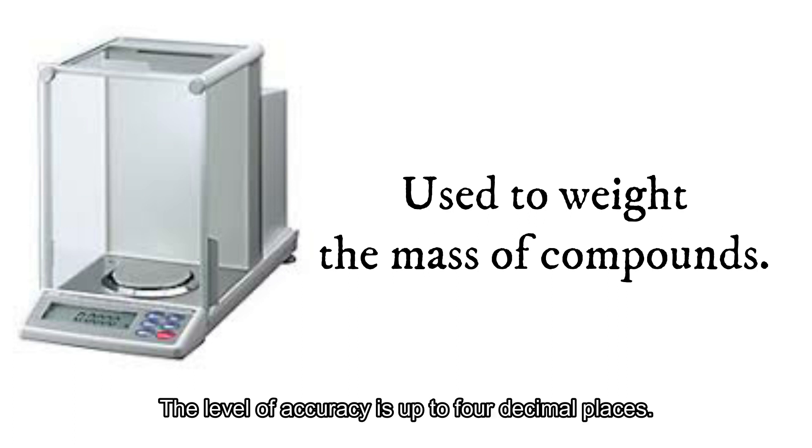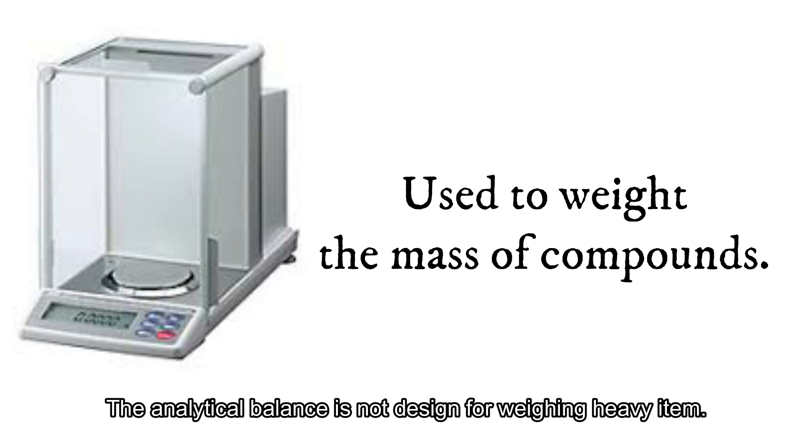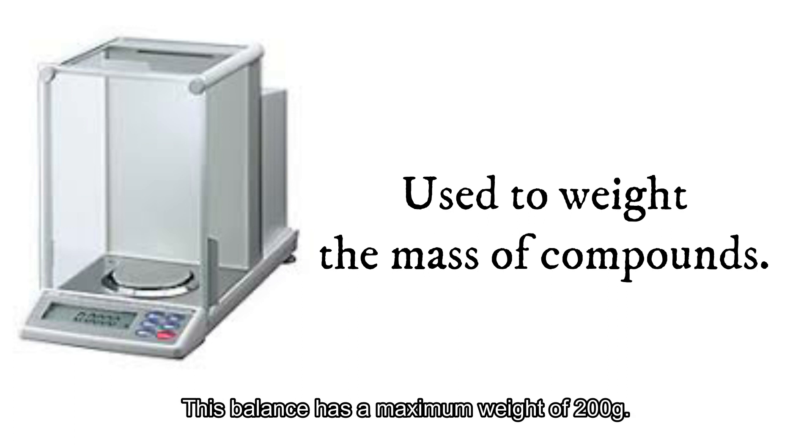The level of accuracy is up to 4 decimal places. The Analytical Balance is not designed for weighing heavy items. This balance has a maximum weight of 200g.